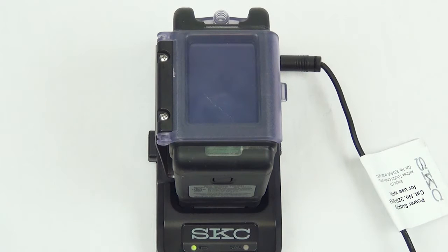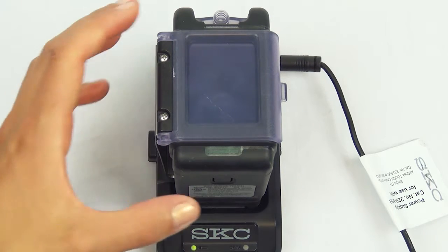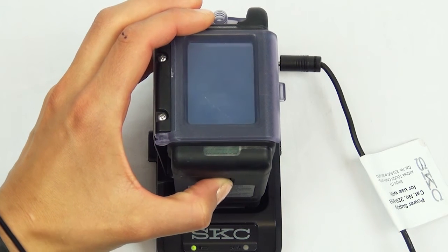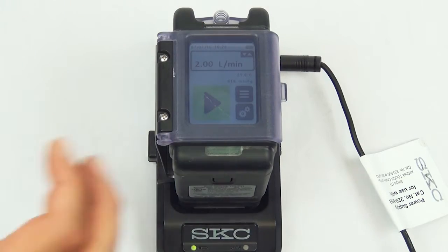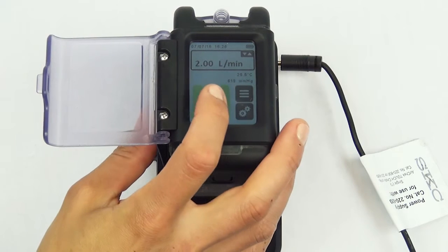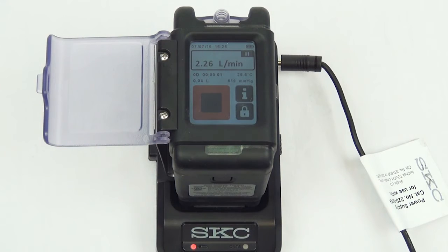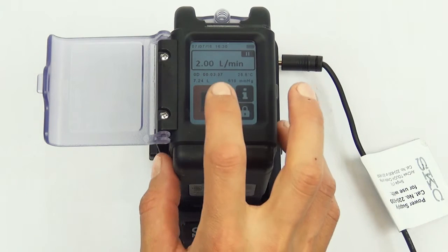Before you start your calibration, you may need to allow the pump to equilibrate if it has been moved from one temperature extreme to another. Make sure to charge the pump battery completely before calibration and sampling. Now touch the Run soft key on the touchscreen and allow the pump to run for 5 minutes. After 5 minutes has passed, touch the Stop soft key.